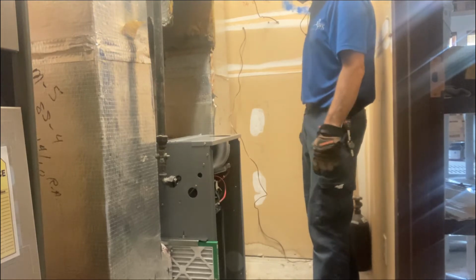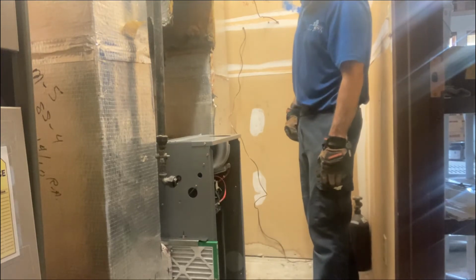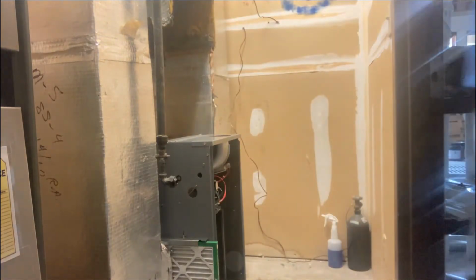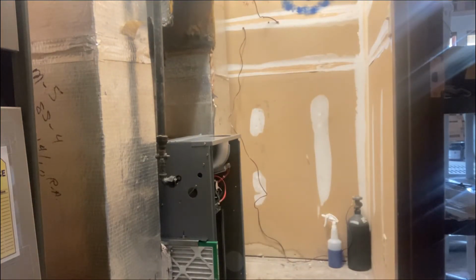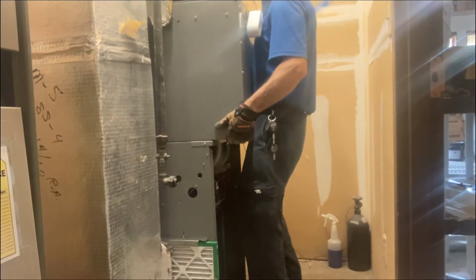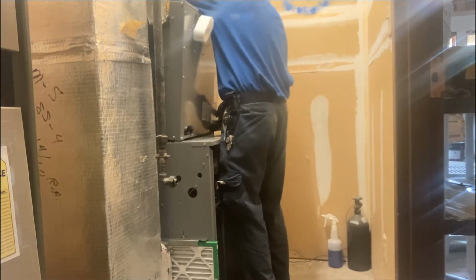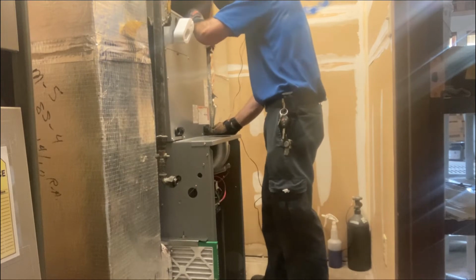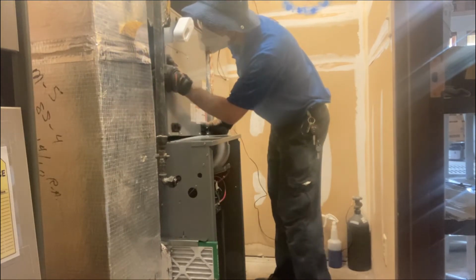When you're installing a new system, you may have to rejigger the supply and return plenums to get them to fit perfectly with the new unit, because this new unit was a slightly different size, dimension-wise, than the old unit. Not a big deal, just keep that in mind if you make it out of ductboard or if you make it out of a metal plenum. So I'm going to actually place everything where it needs to go, set it in position, then I'll reattach my supply and return plenum and get everything sealed up.